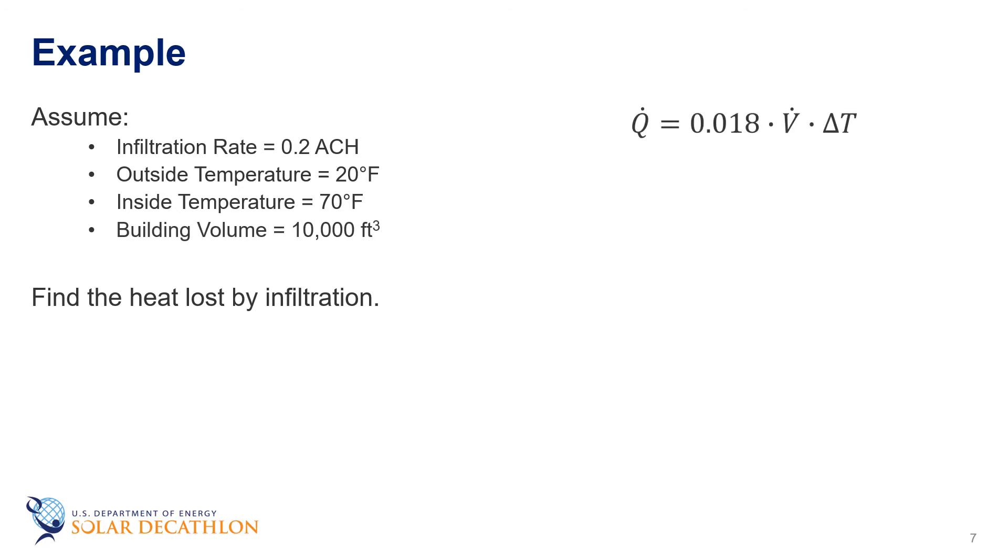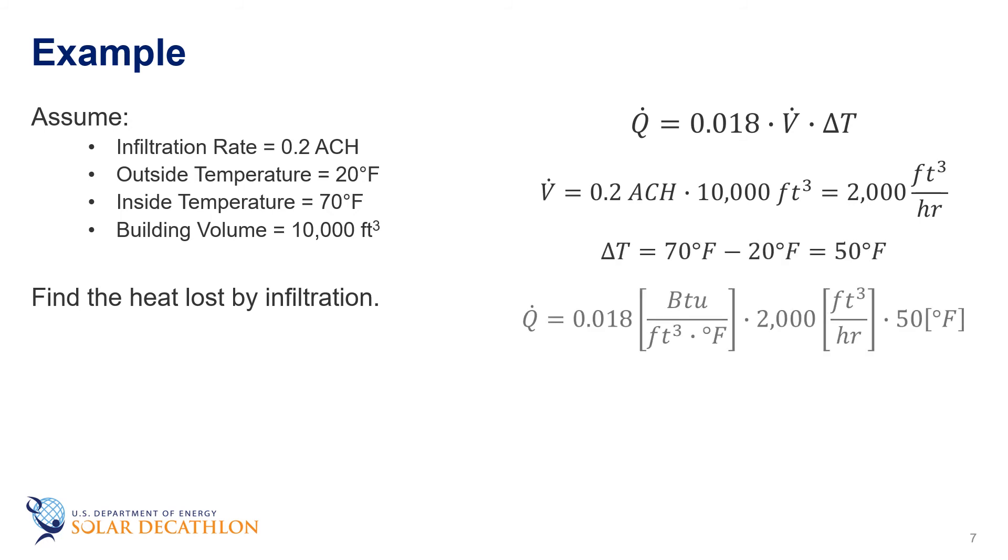For 0.2 air changes per hour, multiply this by the 10,000 cubic feet per air change, and we get 2,000 cubic feet per hour. This represents 1,800 BTUs per hour required for heating.